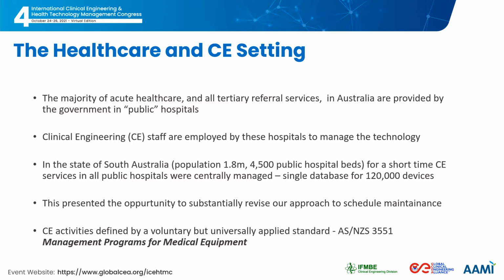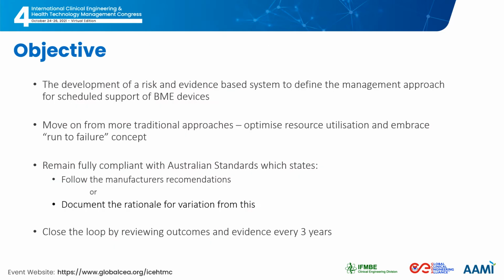We're lucky here in Australia in that clinical engineering activities are defined by a standard as voluntary but universally applied, and that is the Australian and New Zealand Standard 3551, entitled Management Programs for Medical Equipment. That is essentially like a quality system for health technology management, and I'd encourage you just to search that on the internet if you're keen to learn a little more about that standard.